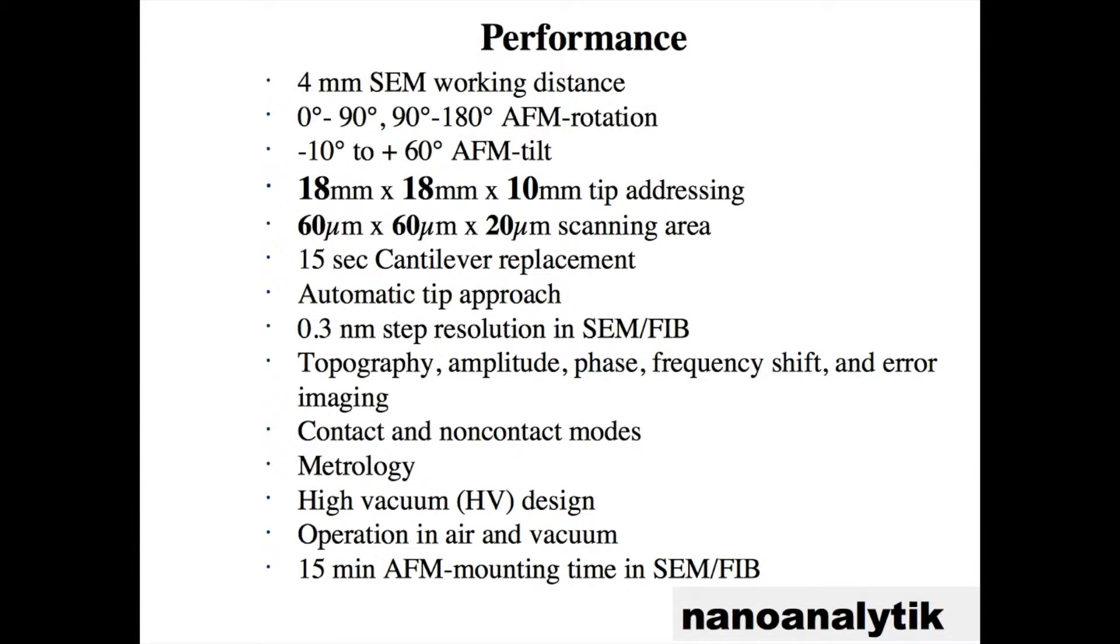The AFM imaging field is 60 by 60 micrometers. Using active cantilevers our system provides a fully automatic approach and it is possible to replace the cantilever in less than 15 seconds.